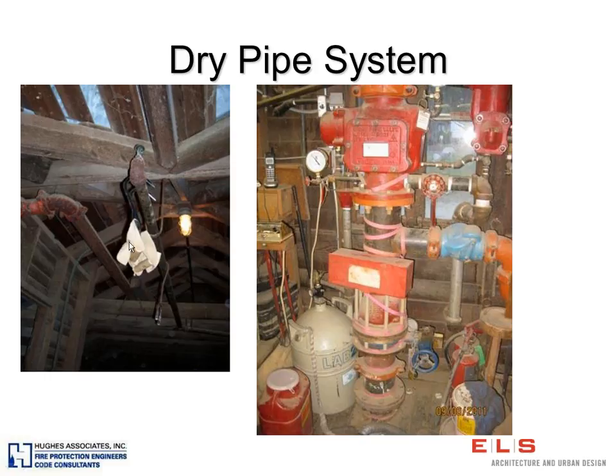But you'll also see that this hay loft is not heated, and you can also see the slats in the roof where there's exposure to the outside elements. And so if we were to put a wet pipe sprinkler system in this application, we'd clearly have freeze conditions and it would be problematic. And so this is actually the dry pipe valve on the right that is protecting this stable.